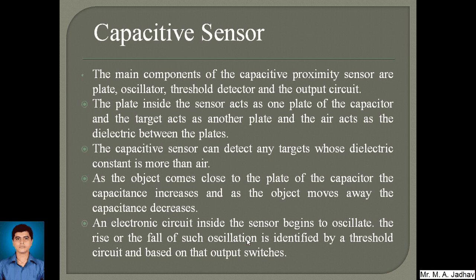The main components of a capacitive proximity sensor are a plate, an oscillator, a threshold detector, and an output circuit. The plate inside the sensor acts as one plate of a capacitor, the target acts as the other plate, and air acts as the dielectric between the two plates. As the object comes close to the plate, the capacitance increases; as the object moves away, the capacitance decreases. An electronic circuit inside the sensor begins to oscillate, and the rise or fall of these oscillations is identified by a threshold circuit which switches the output.